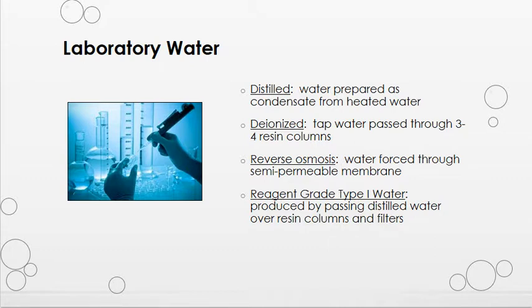There are several different types of water used in the laboratory — specifically type 1, type 2, and type 3 — and type 1 is the most pure. Lab water can be prepared by distillation, deionization, or reverse osmosis. Distilled water is prepared as condensate from heated water; this method removes most minerals, but volatiles such as chlorine or ammonia may remain, and it can be used as type 2 water. Deionized water is tap water passed through 3-4 resin columns; charged particles trap and remove impurities, but this method does not remove all organic materials — most notably, it does not remove bacteria. It can be used as type 3 water, but you would want to consider a different type of water for use in microbiology.